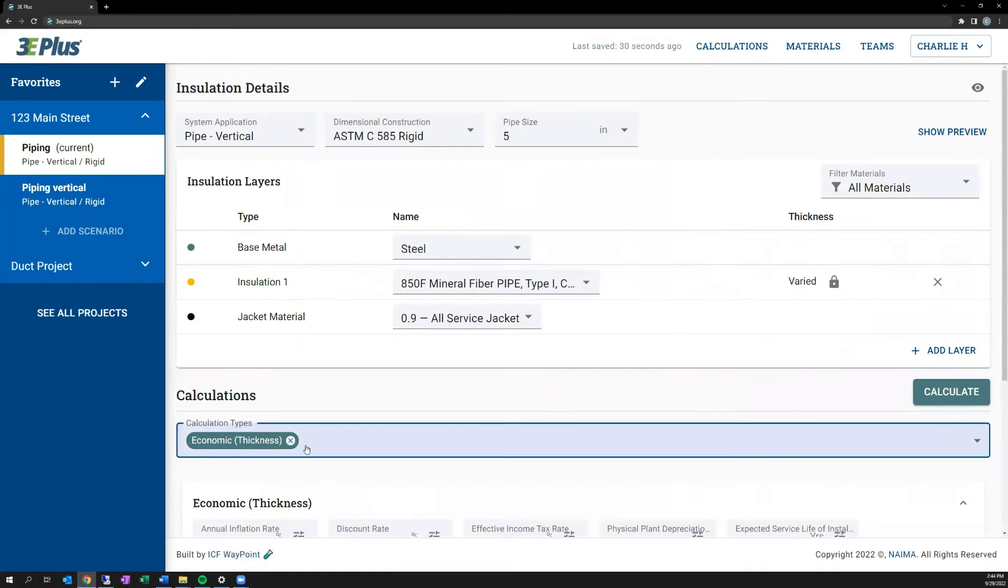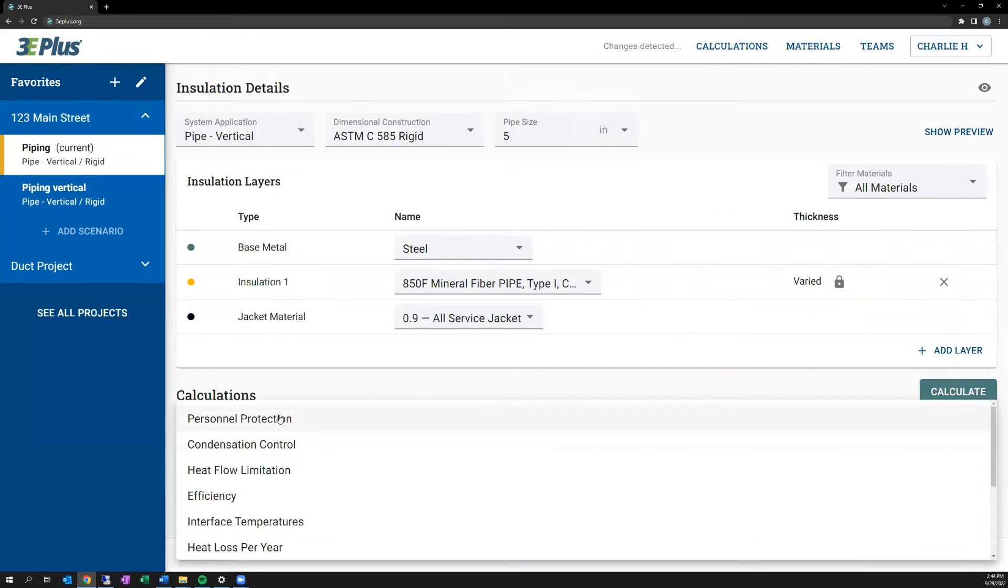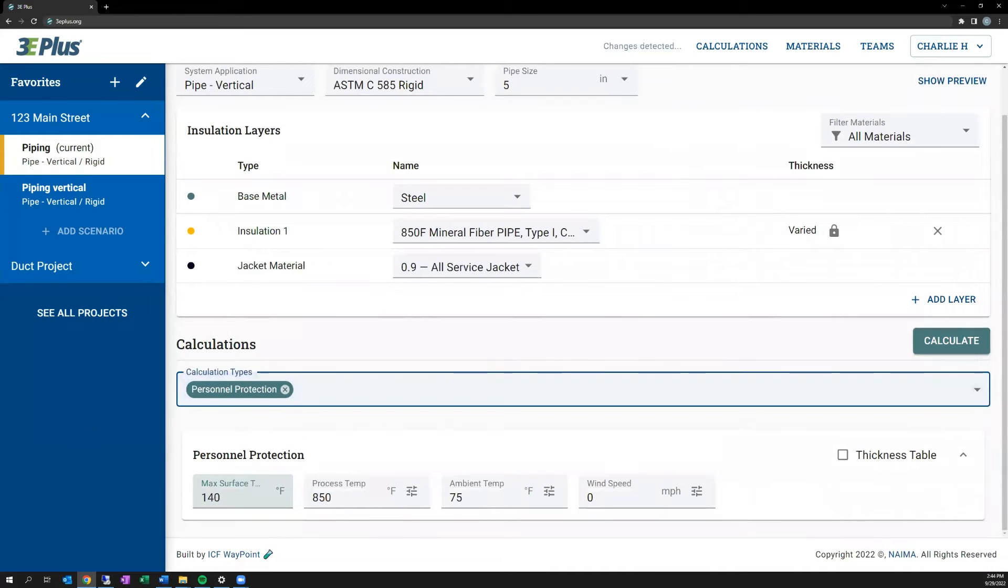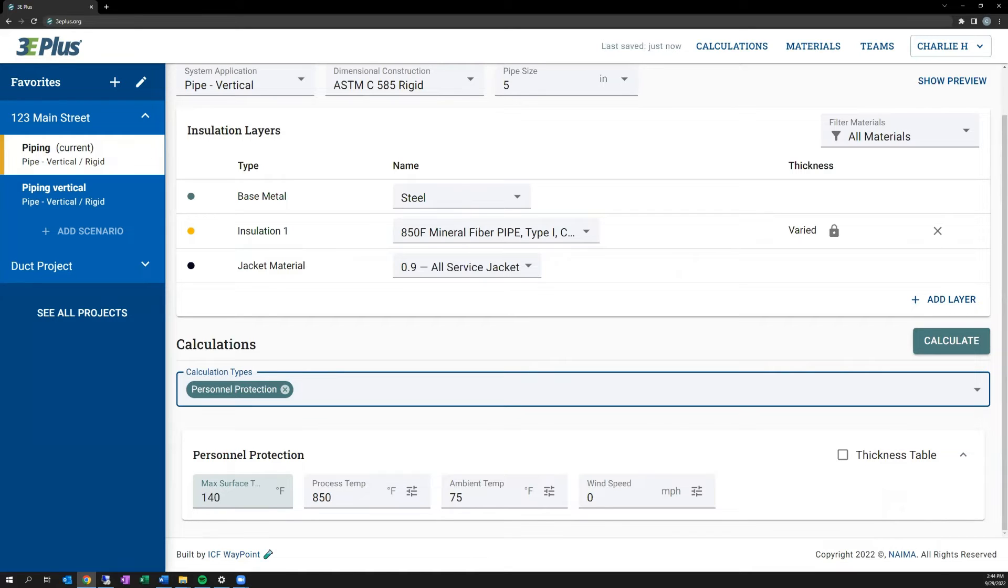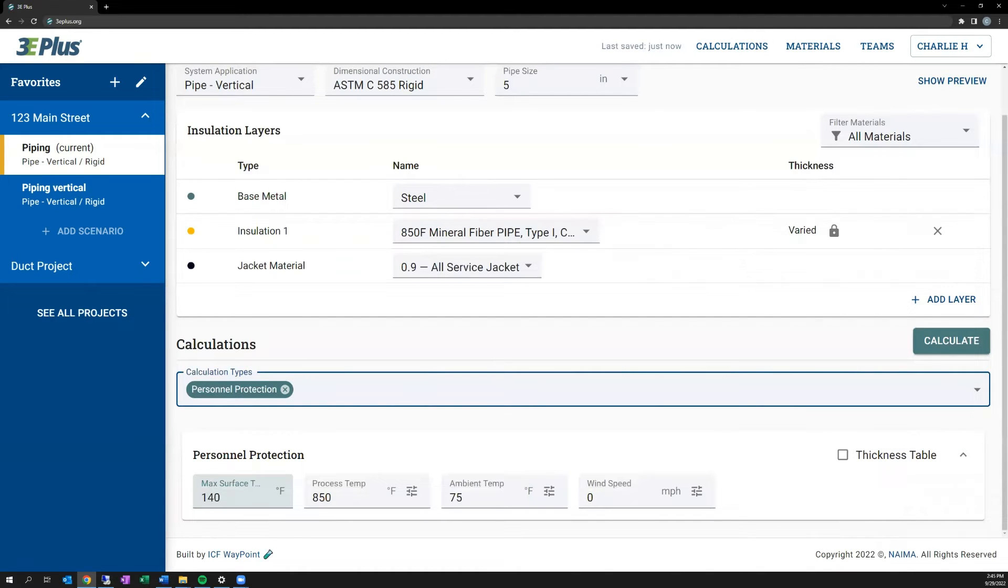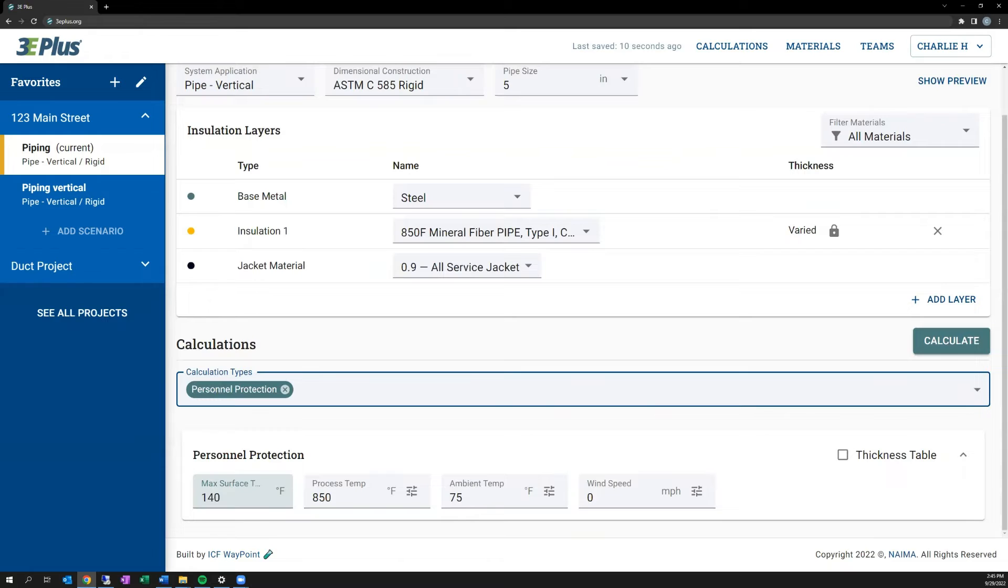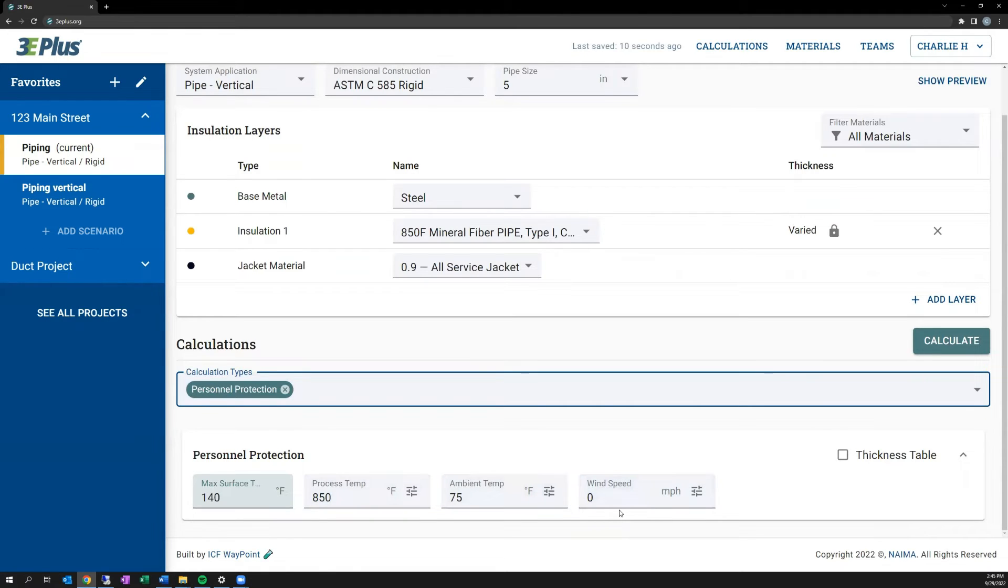So now that we've walked through a calculation that produces a target result that's highlighted, let's talk about the personnel protection calculation. So this calculation type is used to make sure that the max surface temperature on the outermost surface of the pipe did not exceed a set temperature. This protects people in the space from being injured if they touch or lean on the piping. This limit is typically 140 degrees Fahrenheit, but you can customize that here. You'll see that when I add the calculation type, just like with the foundational heat loss calculation type, it also calls for process temperature, ambient temperature, and wind speed with air around the pipe.